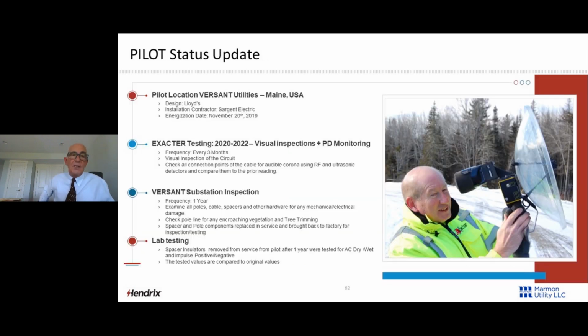And what we did, in a status update, when we built this pilot with Versant, with EMERA in Maine, we had a company called EXACTER come in for testing. They did visual inspections and PD monitoring every 3 months, a visual inspection of the circuit, and checked all connection points of the cable for corona using RF and ultrasonic detectors, and compared them to previous readings. These EXACTER guys know what they're doing with this kind of monitoring. We did a substation inspection at a 1-year frequency, examining all poles, cables, spacers, and other hardware.